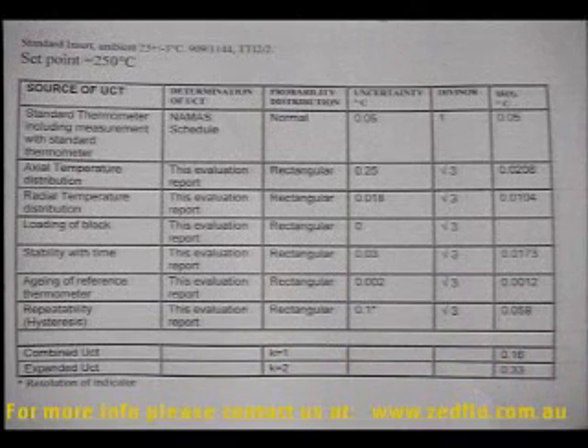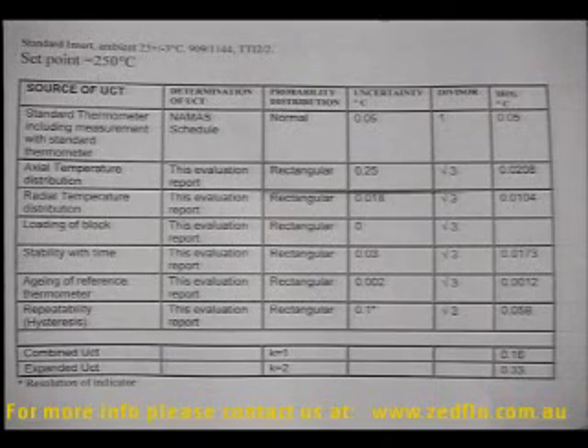So you can see how very important it is to have the built-in or external measurement of what is happening inside the insert as you put in or take out different temperature sensors. On this sheet, you will see the total combined uncertainty of all the different errors that can come into play while we're trying to do a calibration. I'm not going to go through it in detail. It's basically a worst case.